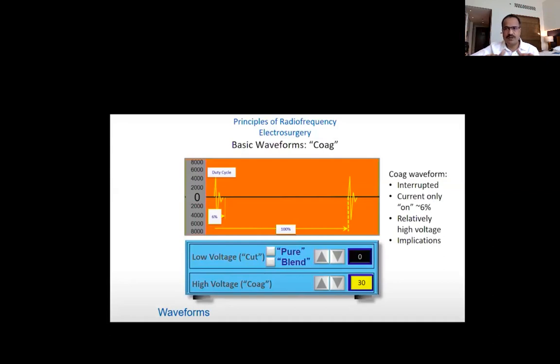Okay, very simple. This is a very simple understanding. So now don't imagine what is cutting or coagulating. These are just names unfortunately given to the currents before it was discussed with the medical language. So we have to just take them as currents. Here you have to understand that the cut current and the coagulation current or the blended current, which I will discuss, all have the ability to cut the tissues, that is, vaporize the tissues, and all have the ability to coagulate. That means, in our routine words, to make a clump, to desiccate in the real meaning.